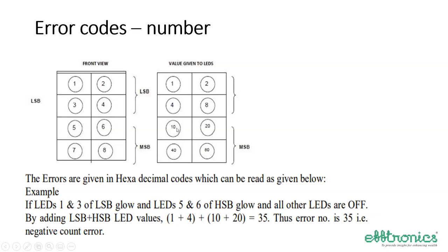For example, in one of the failure cases, 1 and 3 are lit, and similarly 5 and 6 are lit. So what should be the number? 1 and 3 means 1 plus 4, 5. And 5 and 6 means 10 plus 20, 30, 35. This gives the second digit. The top one gives the first digit. Like this.